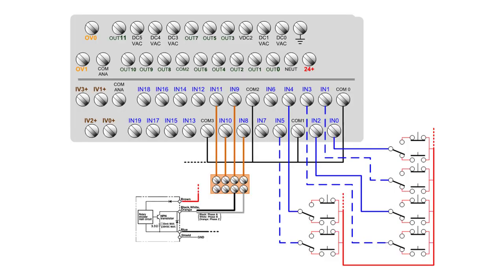Earlier we showed you orange connections and we mentioned that was for high speed counters 8, 9, 10, 11. That is a complete full speed counter input that we're using. A lot of these controllers have 6 high speed counter capability, but not full. It's either 3 full or 2 full, or 6 halves. So you can have 6 high speed counters with this controller, but they're not full high-speed counters with all 4 input connections. Now, in this case, we're only showing you the phase A and phase B of an encoder hooked into input 8 and input 9. So we're not even really demonstrating the full capability of a high-speed counter in a MicroLogix 1400.